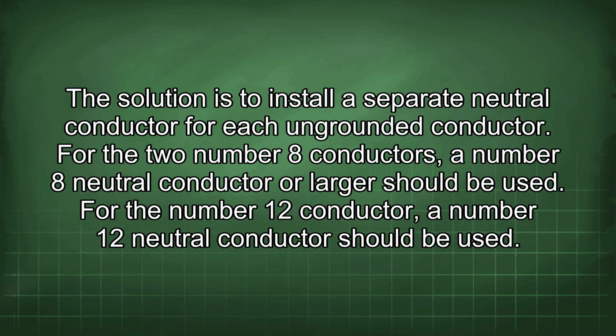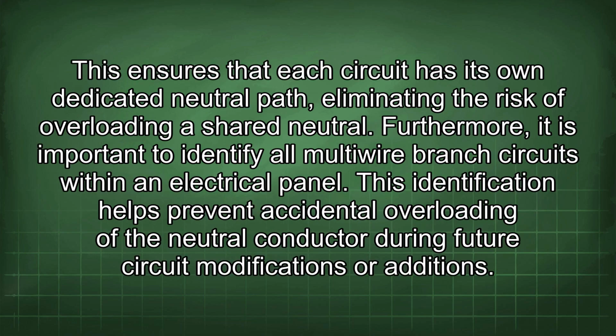The solution is to install a separate neutral conductor for each ungrounded conductor. For the two number 8 conductors, a number 8 neutral conductor or larger should be used. For the number 12 conductor, a number 12 neutral conductor should be used. This ensures that each circuit has its own dedicated neutral path, eliminating the risk of overloading a shared neutral.